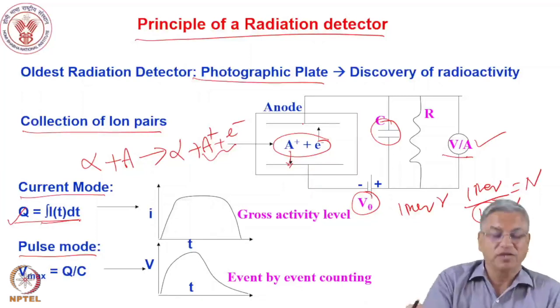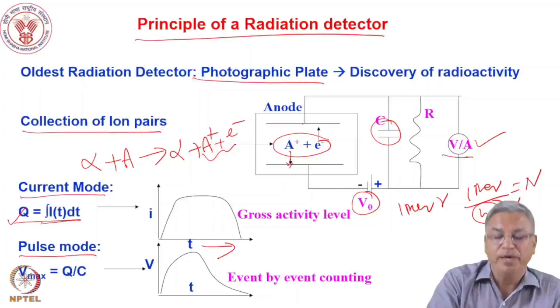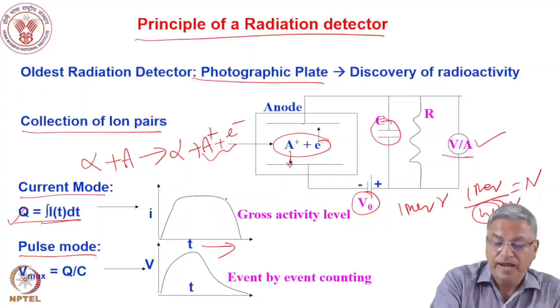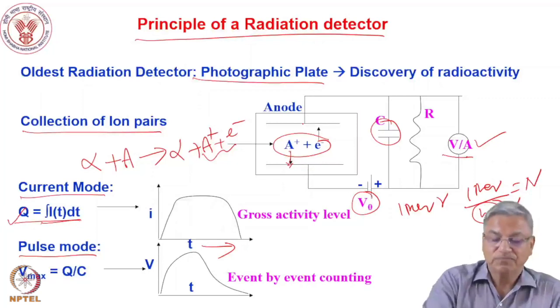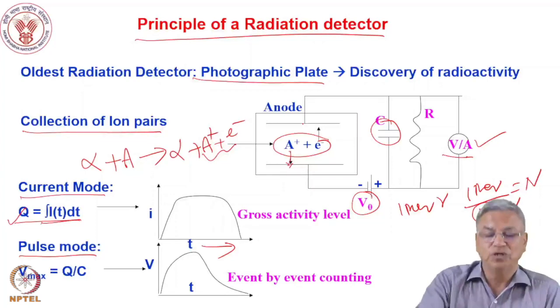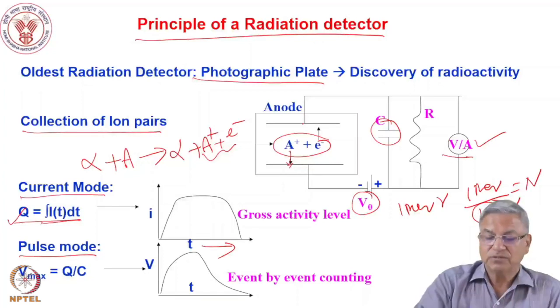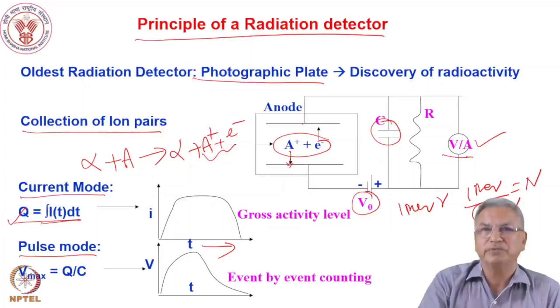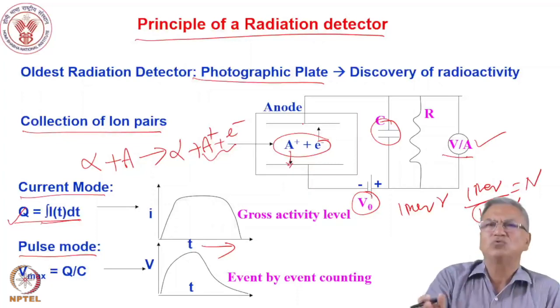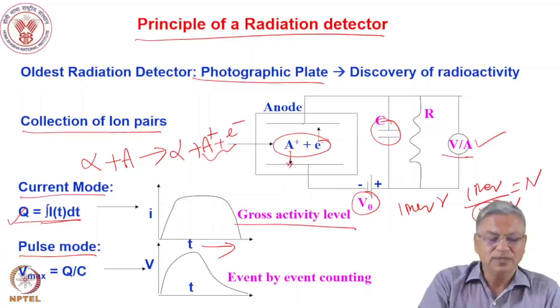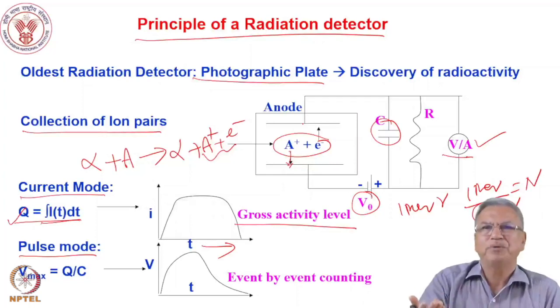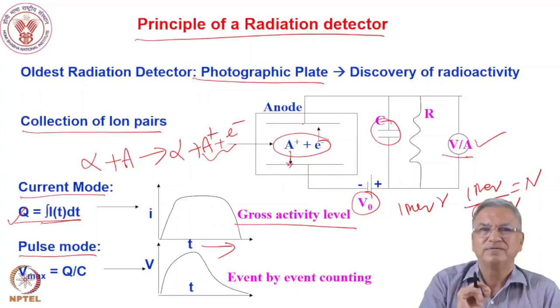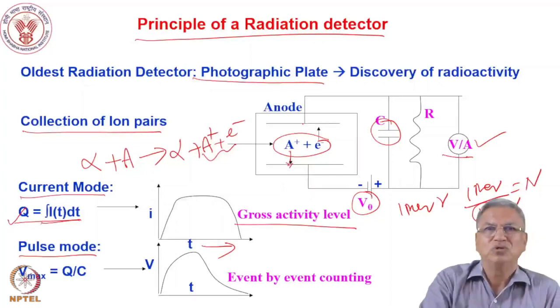Multiple events lead to a flow of current in the circuit. This current mode mechanism is not used for counting activity but gives you the gross activity level, like a survey meter in the laboratory. The current level — how many microamps, nanoamps, milliamps — tells you the level of radiation. But if you want to count the activity quantitatively, how many counts per second, then you require pulses. So you need to shape the pulse.